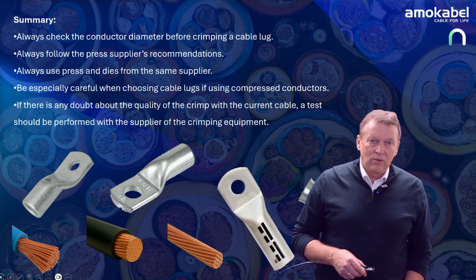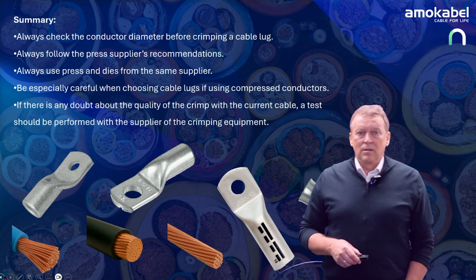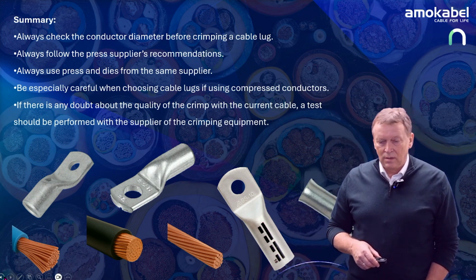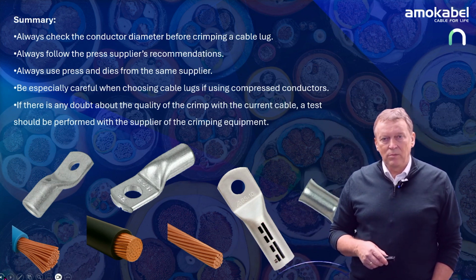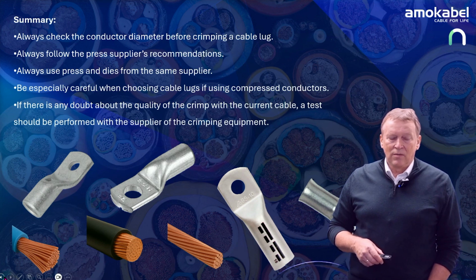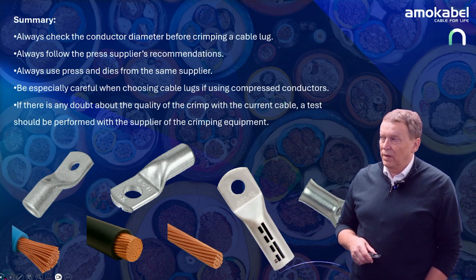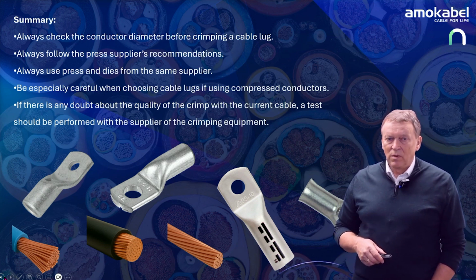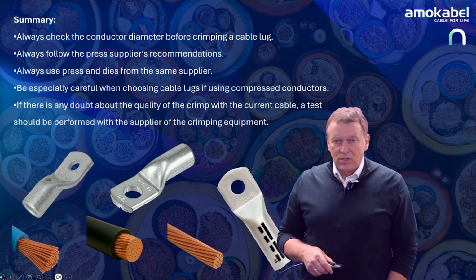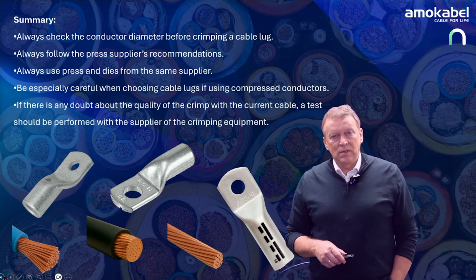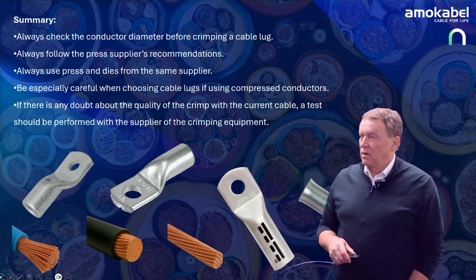That's a typical pull-out test. So see that it follows the demand of how many Newton meters you shall have in the cable lug when you take out the cables. You can also do some vibration test on the cable lugs to ensure that they can resist the vibration as well.